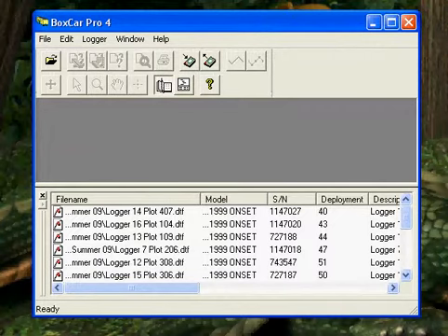Now, on the data loggers themselves, if you look on the bottom edge of the box, you can see where there's a place to take out a little plug using a screwdriver. That plug has an O-ring on it. These boxes are used out in the field, so they have to be weather tight. So you'll see a little black O-ring on that is used to seal it tight. Plug in the miniature phone jack, the 1/8 inch miniature phone jack that you see is already plugged into the back of the computer on the COM port.